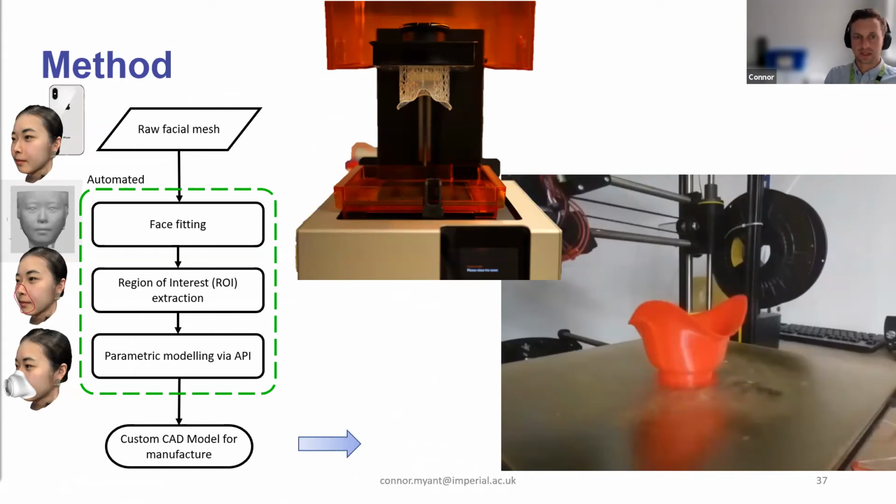So typically a face mask will be done using a hot pressing process for the stiff fabric based ones, or an injection molding or casting process for the polymer elastomeric masks. Those molds that are needed in either of those processes are very, very expensive and very hard to manufacture in the first instance. So you don't want to change the design of your product, because you're going to have to pay that cost again. And that again is the whole thing in a nutshell of modularization.